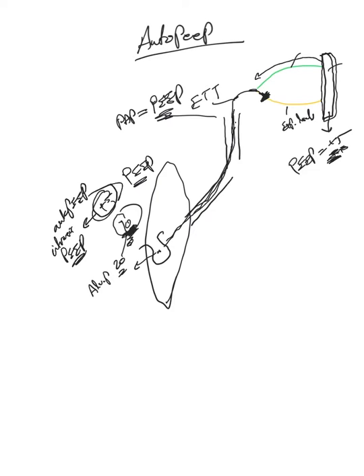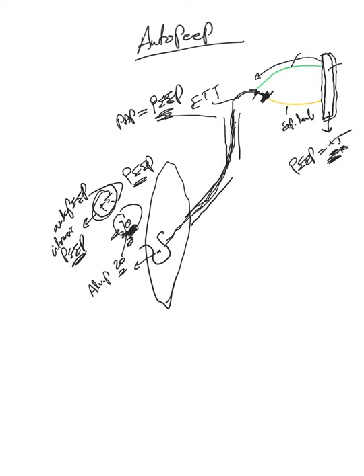So we close this valve. Now, the air will cease and the flow out will cease in. The ventilator has not given any positive pressure to reverse the flow back in. And give it a little bit of time, give it a pause. The pressure here will equilibrate and the sensors here will measure the alveolar pressure at that point.